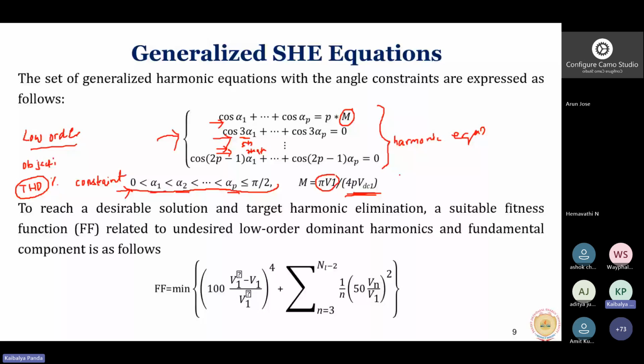So for this total harmonic distortion to reduce, the major question comes: can I take THD itself as the objective function? If you take THD itself as the objective function, you will not be able to do two things. First, you will not be able to maintain the fundamental value, and at the same time you will not be able to eliminate the selective order of harmonics. Why? Because THD is a total sum of all harmonic orders in comparison to your fundamental value. So taking THD as the objective function is not the right choice.